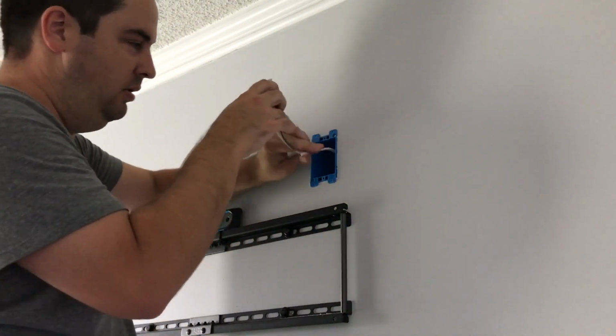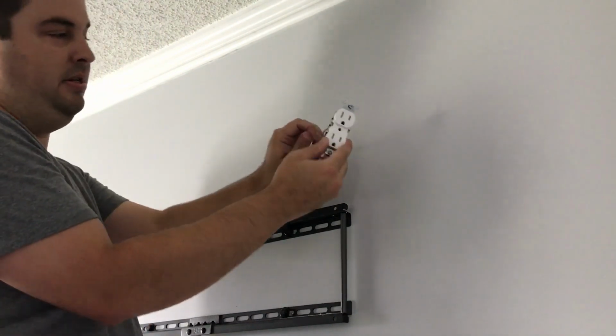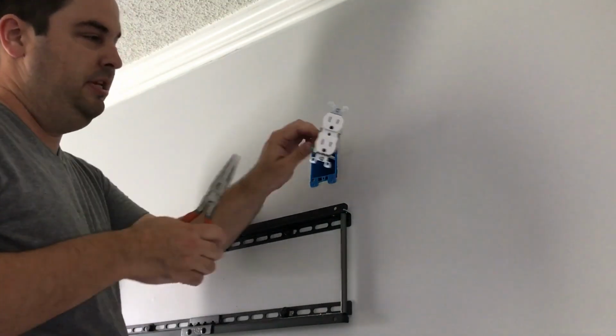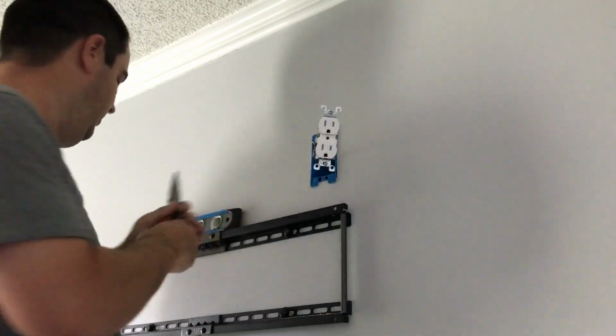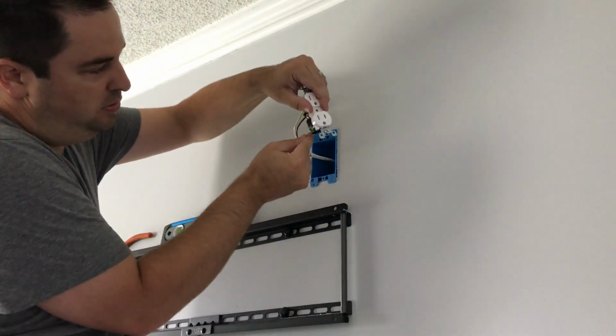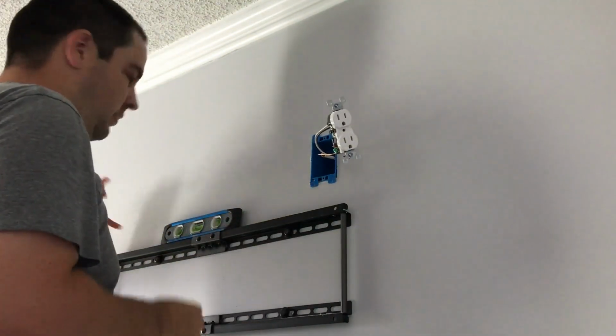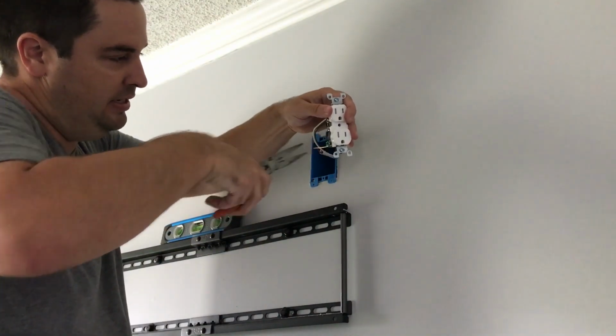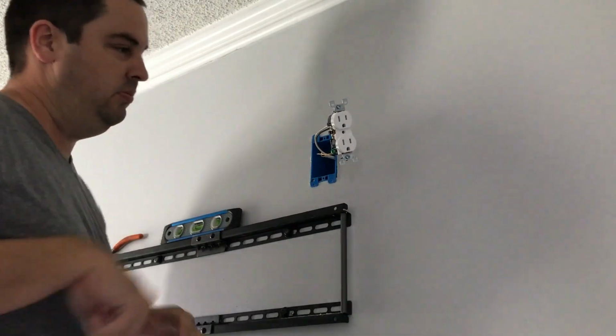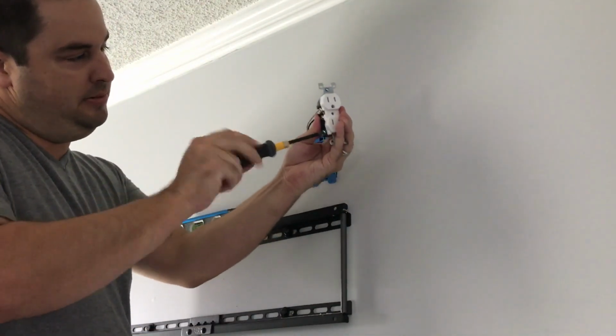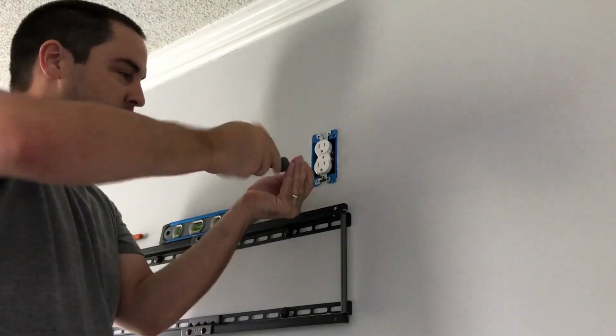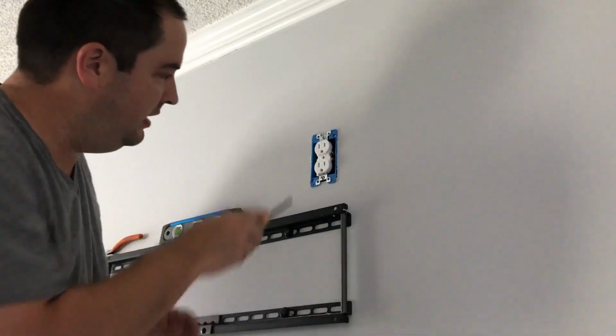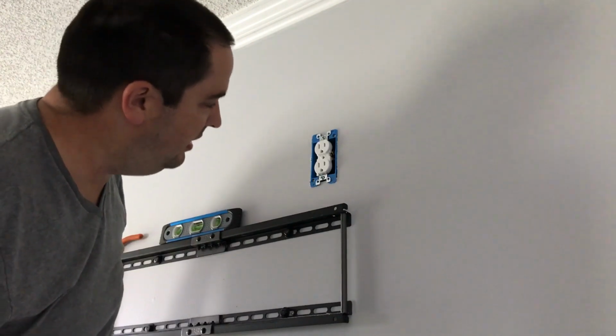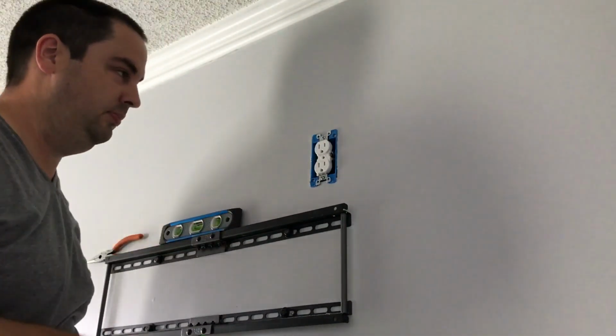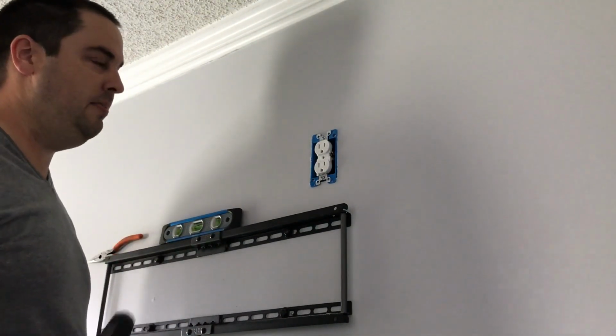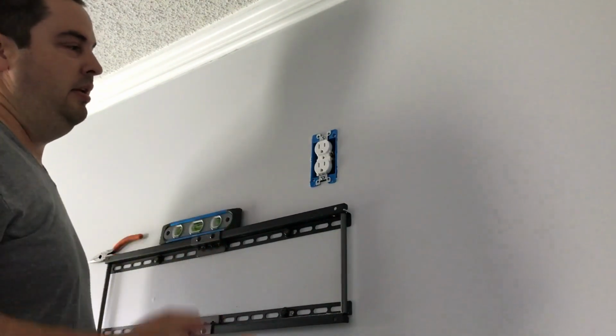There, put the rest in there. Now I need to take the ground and essentially make a circle with it. Screw the ground in, obviously. It's tight. Good to go there. All the way. And now, make sure the ground doesn't touch the outside. And there we go. We have an outlet now. Now, one thing is, we'll hook it in on the bottom, and I got a tester that'll test it and make sure the ground works, hot, and the load side works correctly.